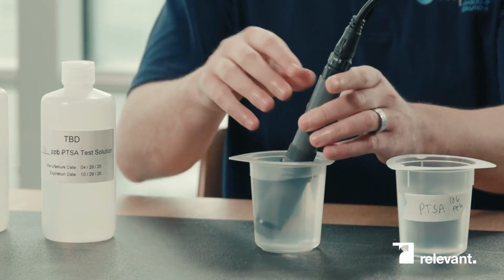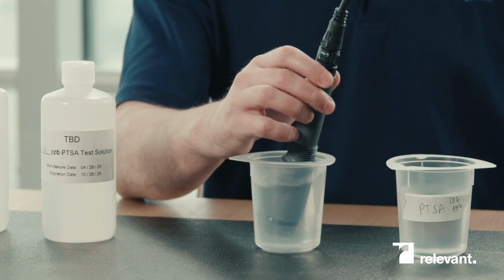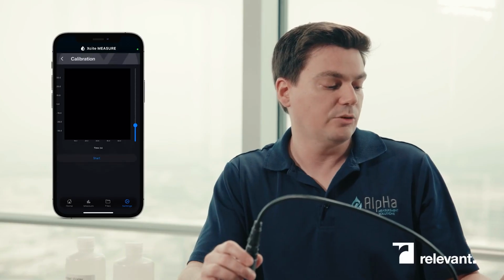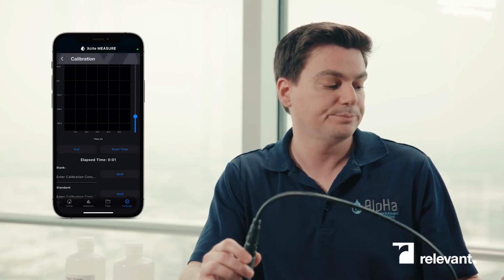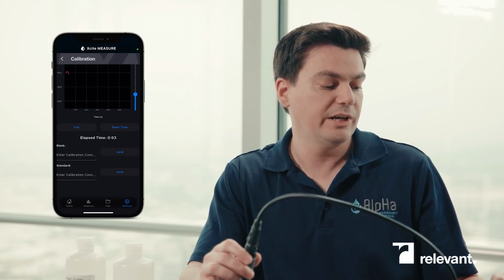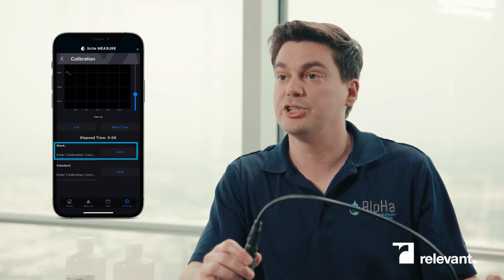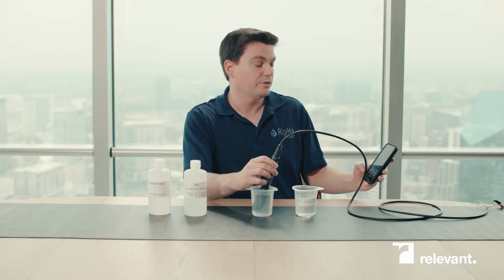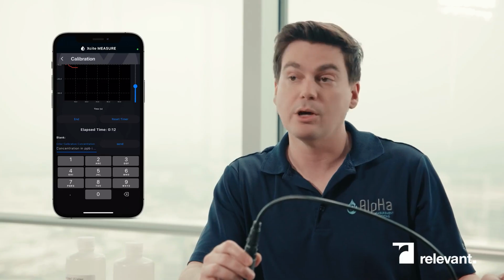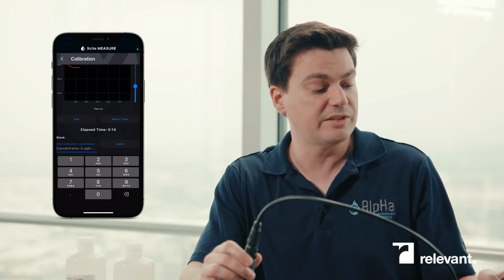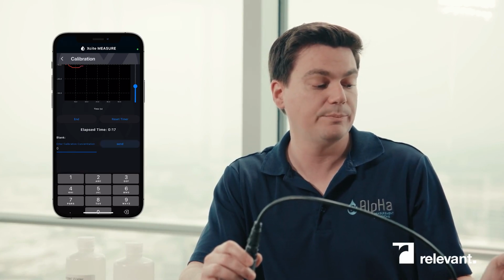Somewhere in between the entire measurement range is preferred. In this case, since the measurement range can go up to 650 ppb, we're going to pick a known standard of 186. So the very first thing you do is put the PTSA sensor in the blank, as shown. Once you do that, on the application itself, you'll hit the start button. And then right down over here on blank, it's enter calibration concentration. Since your blank is a 0, the number pad will come up right over here and you'll hit 0 and then send right next to it.